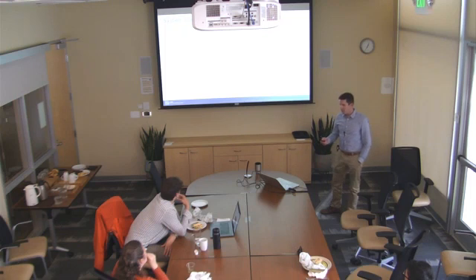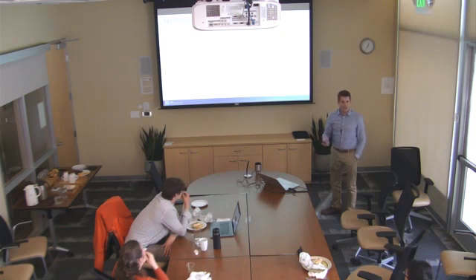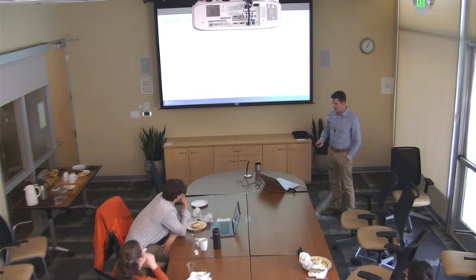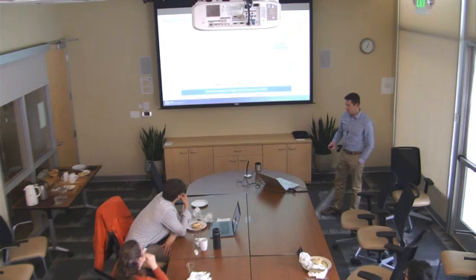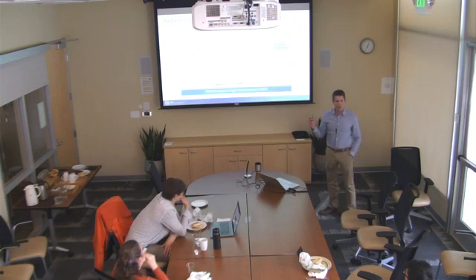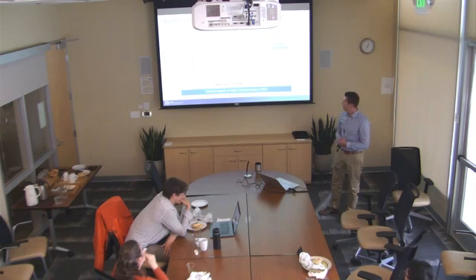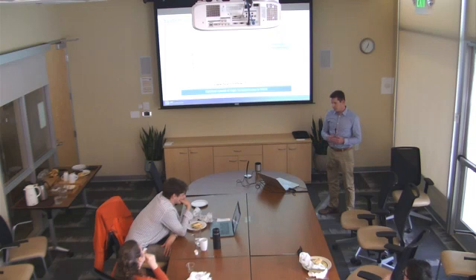So now I'm going to talk about system COP, and this is the system performance. This is essentially, if you were going to include the equipment and the duct performance together into one metric, that's what we're doing here. So it describes the overall system performance of the equipment and ducts. And what you see is if you combine these, there's different optimal speeds depending on the temperature of your outdoor air or attic zone, as well, and temperature outside, and the speed of the equipment.